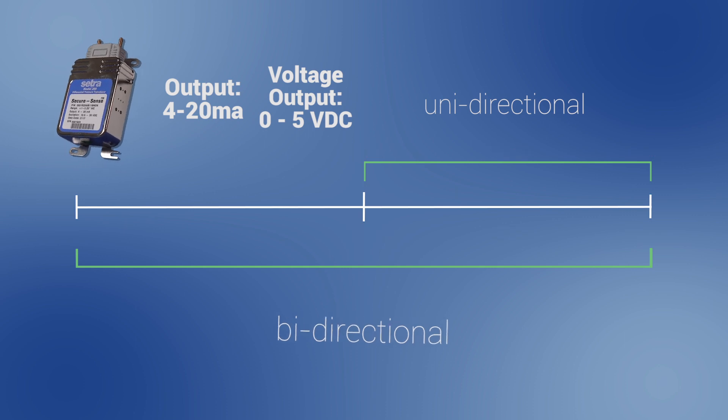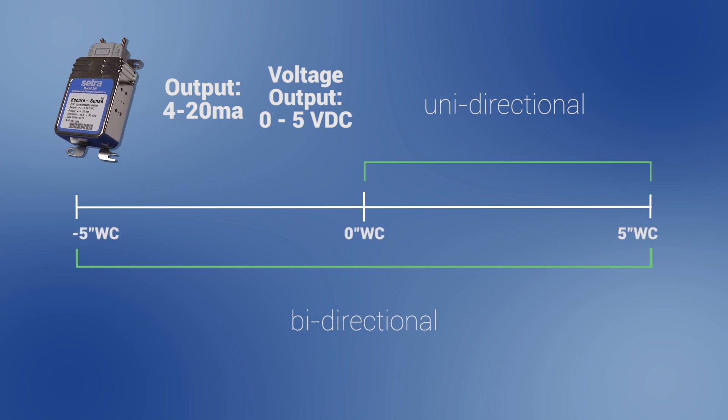If the unit is a bidirectional range like plus or minus 5 inches of water column and 0 to 5 VDC output, the unit would output 0 volts at negative 5 inches of water column, 2.5 volts at 0 inches of water column, and 5 volts at positive 5 inches of water column.